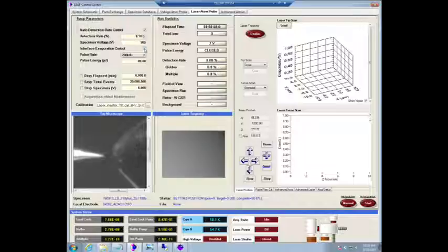Then there's something called interface evaporation control, or IEC. What the interface evaporation control does is measure, within a certain period of pulses, the average number of atoms it gets per pulse. On the older systems, it was 10,000 pulses. On the 4,000 systems onwards, it's 10 pulses. So if it suddenly gets a lot of atoms per pulse, it will just step the voltage down by a predefined value, usually 3%, 4%, 5%.